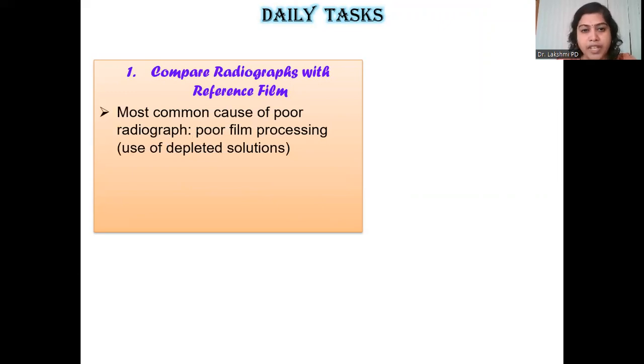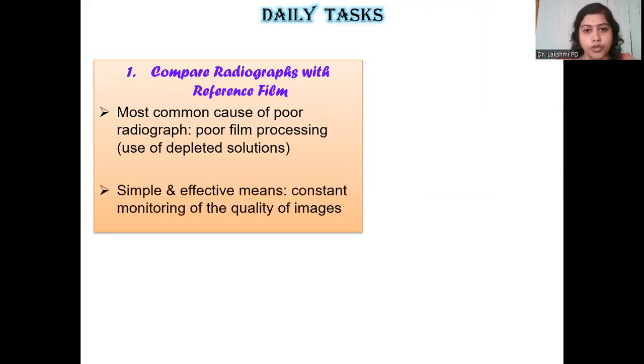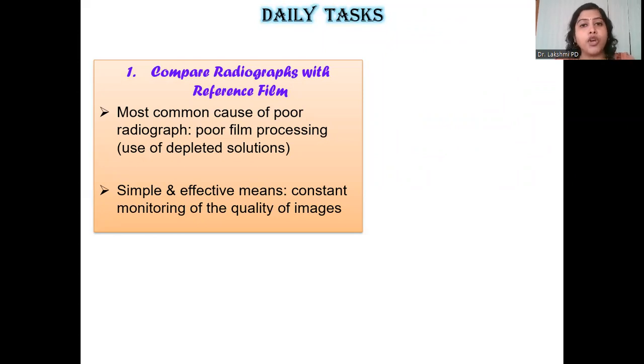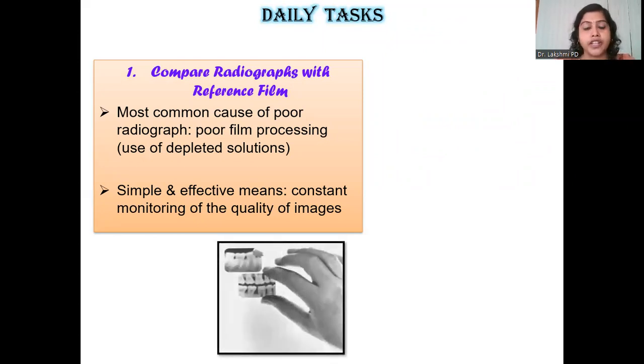This is the most inexpensive way to make sure that every single film given out from your radiology facility is of optimum quality and optimum density. One of the most common reasons for poor radiographs not of adequate diagnostic quality is because of poor film processing, especially because of the repeated use of depleted solutions. So to overcome this, you have to constantly monitor the quality of your radiographs being given out from your facility.